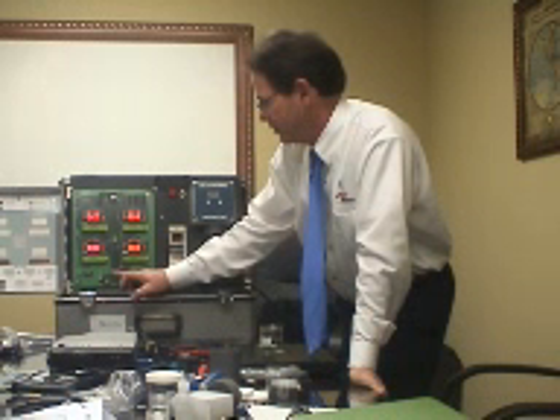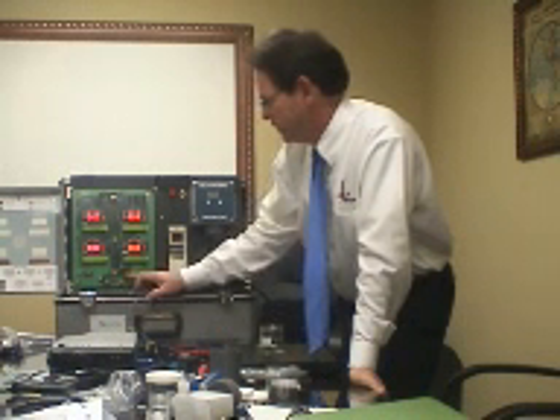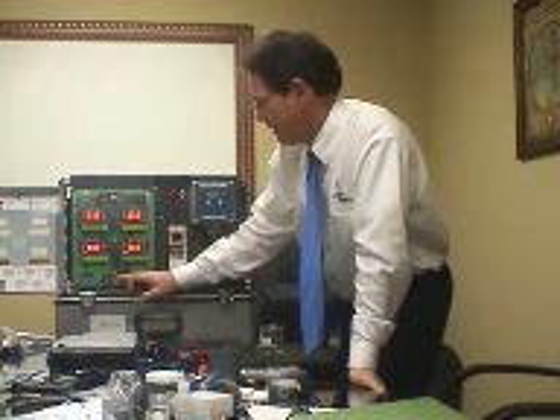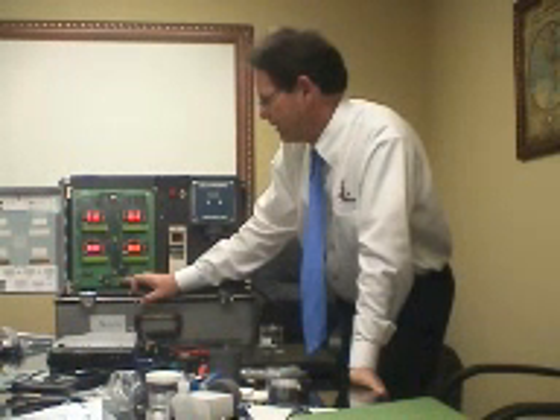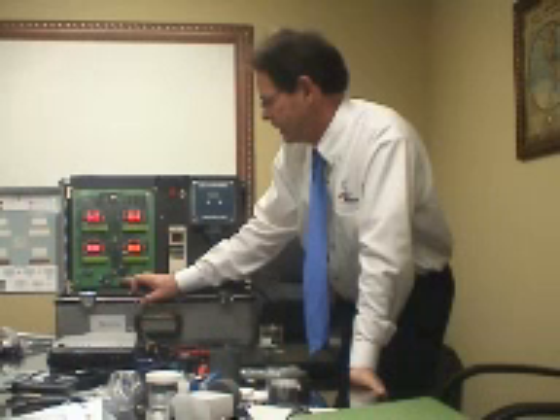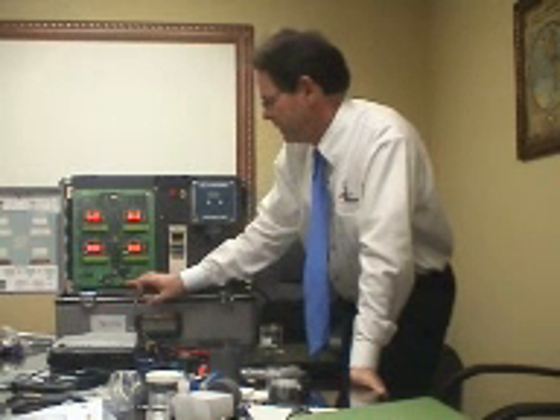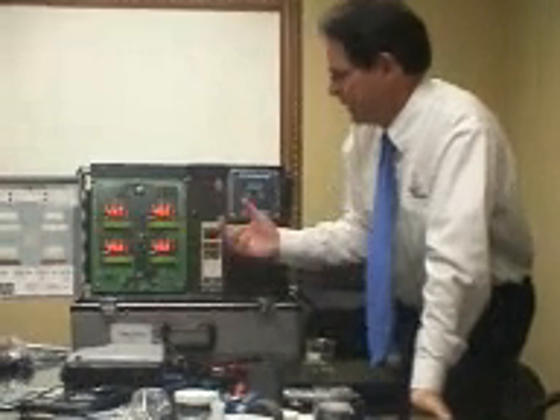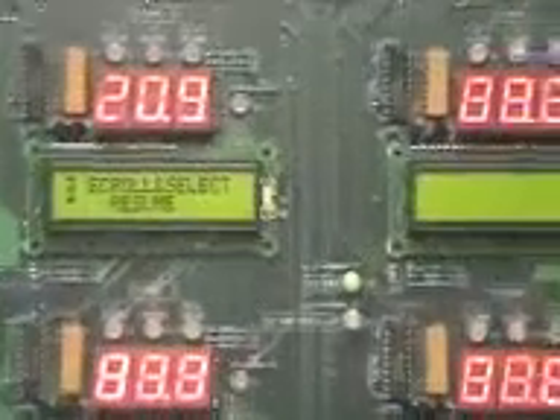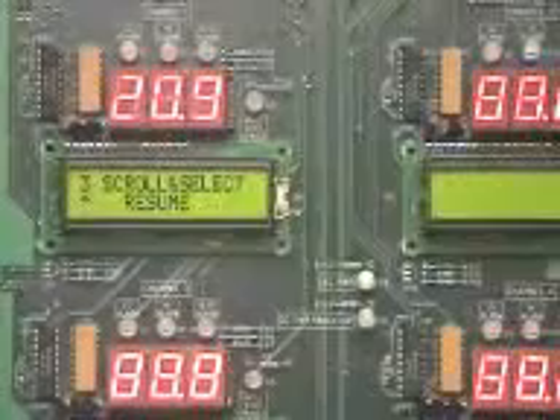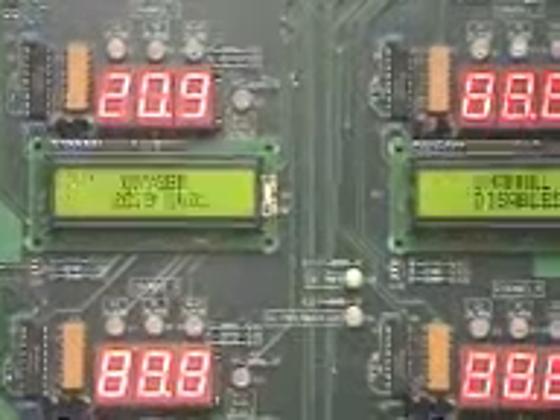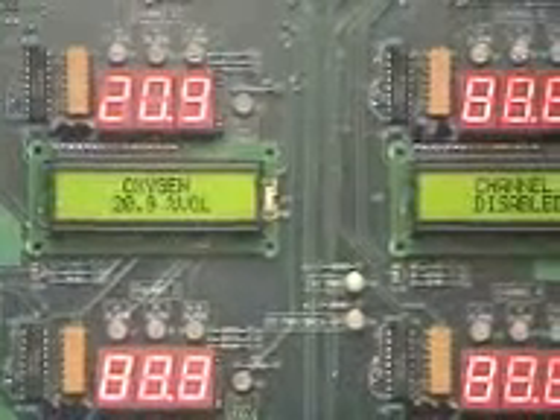Select the channel one more, please. And then go to next. And go down. There's something here called the zero adjust. There it is. Zero adjust. We want to do that. And it synchronizes the 2 milliamp signals. So it has a better, and go down to where it says resume and select that. So we have a reading of 20.9.